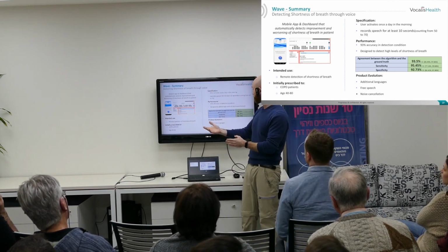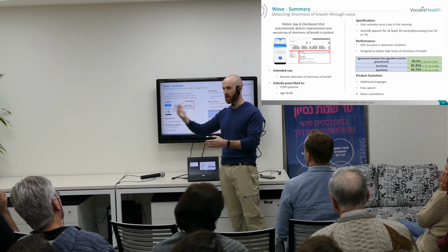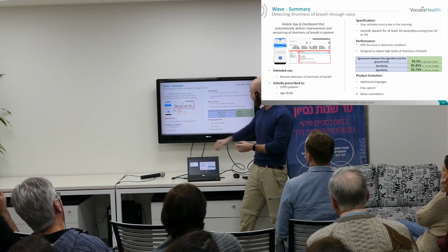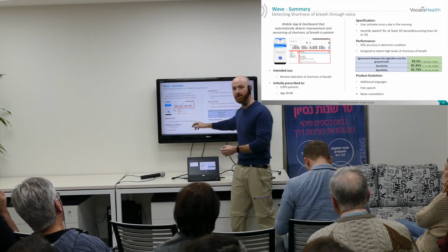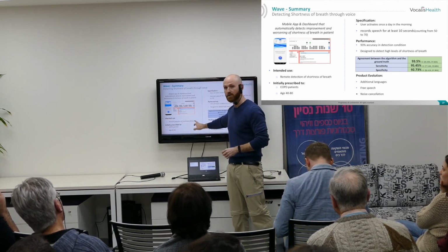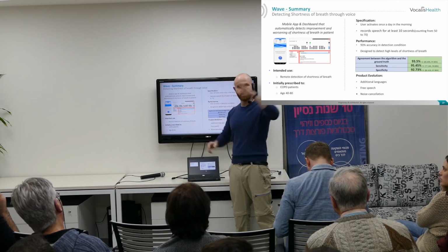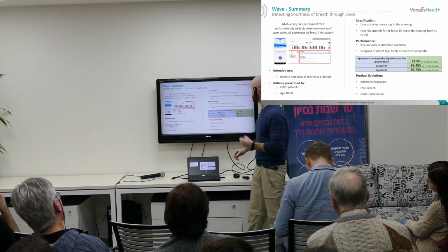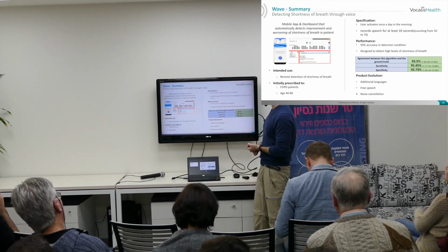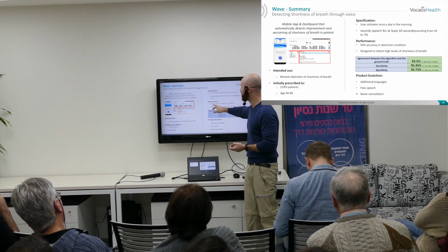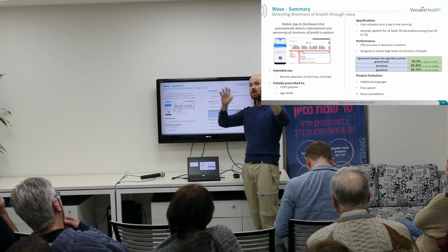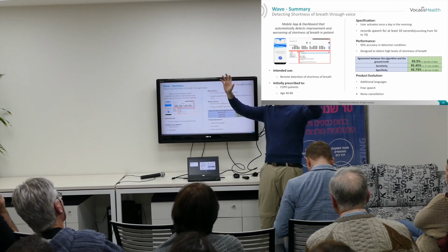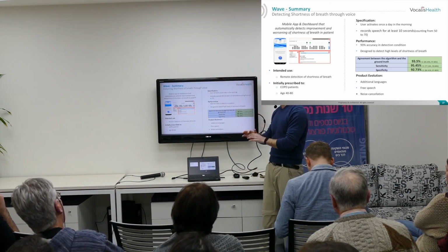That also tells us what kind of class, meaning if you go to the FDA in the US or CE mark in Europe, how you describe what the product does depends on the class. So if we add monitoring here, then we'll be in a different class. There's a lot of work with the regulatory advisor on how to define the product and the performance. This is the performance of the total product, not just the breath and speech classifier, but the one that compares pairs and tells if they are better, worse, or same.